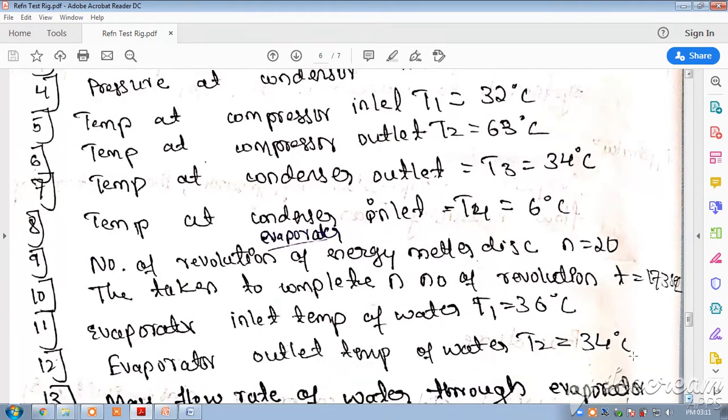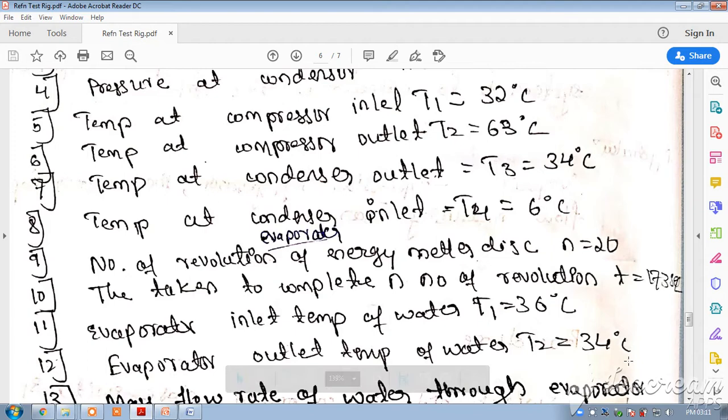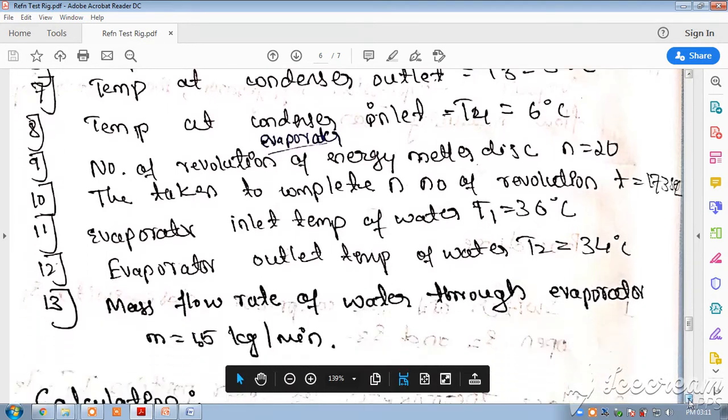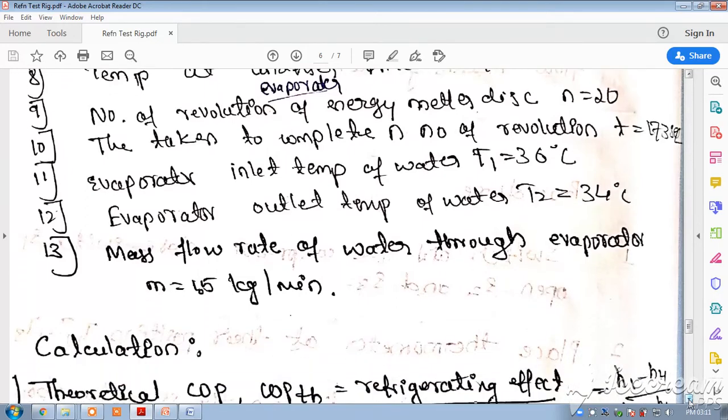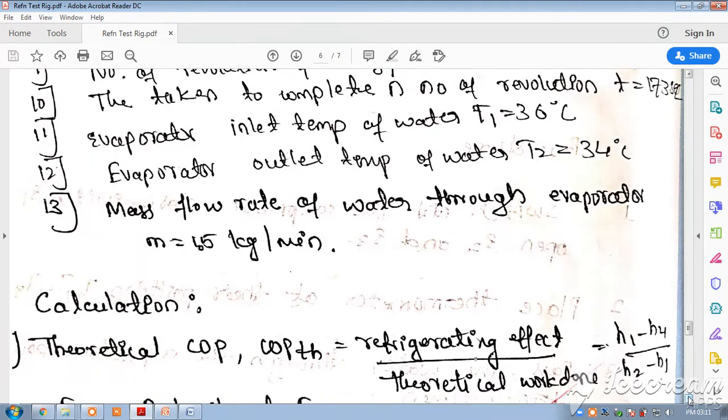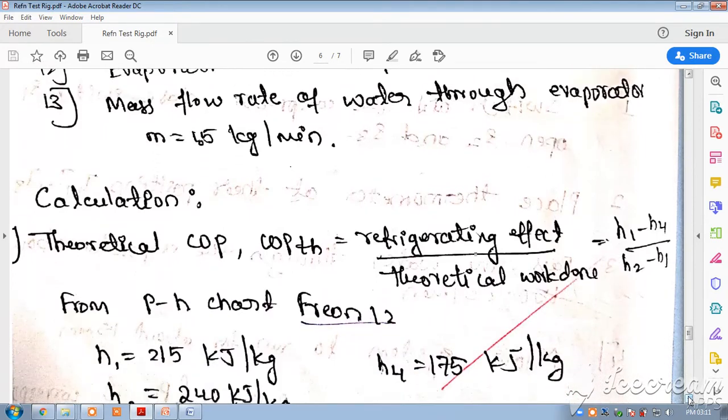We also measure temperatures at the compressor inlet, temperature at the compressor outlet, condenser outlet - all these temperatures are measured. Then the energy meter - the revolutions of the energy meter, the time taken by the energy meter, and the evaporator outlet temperature are taken.